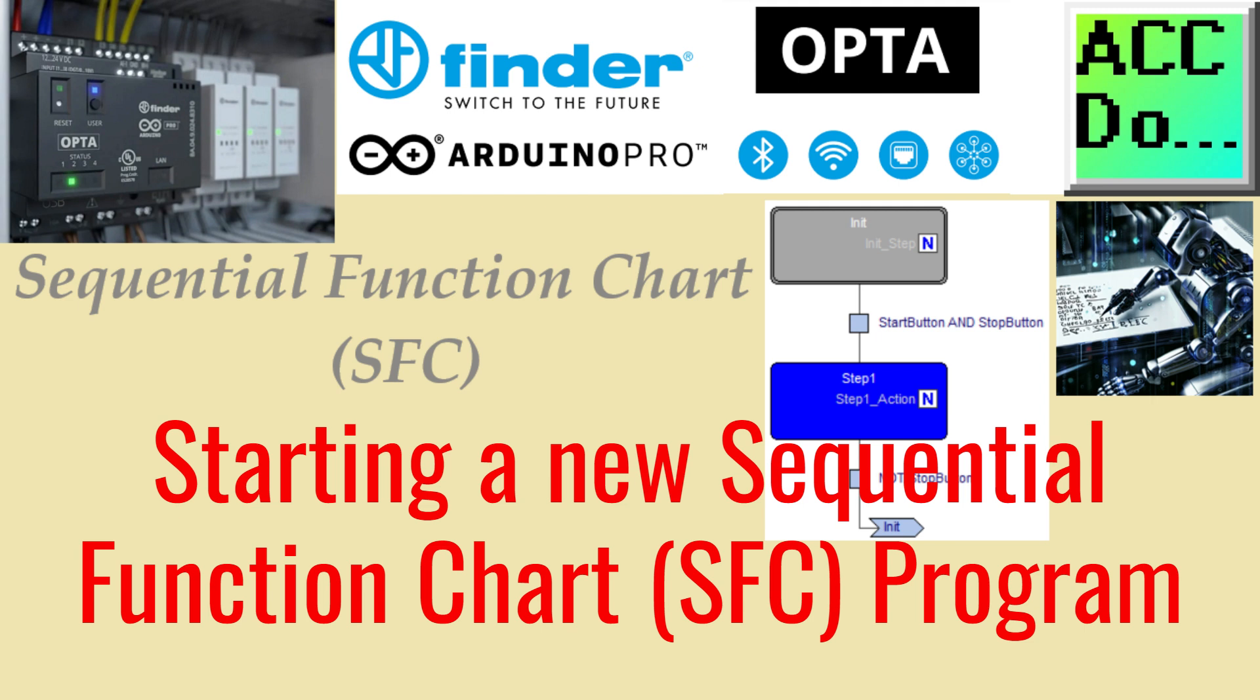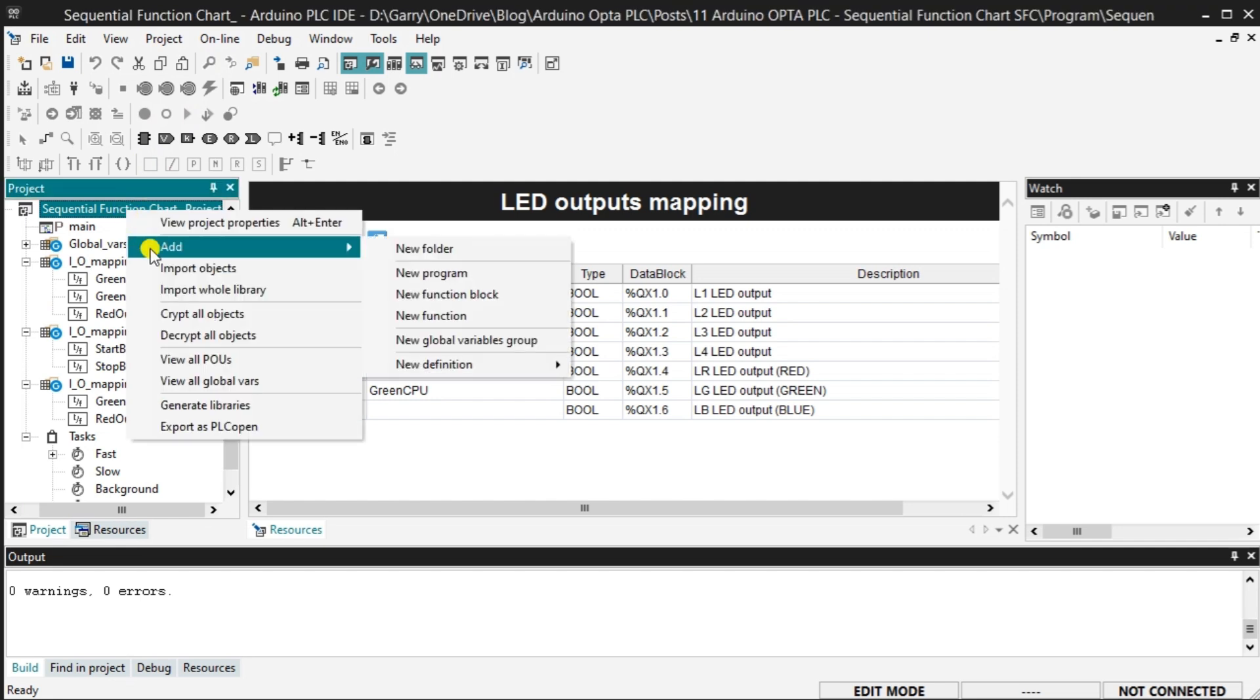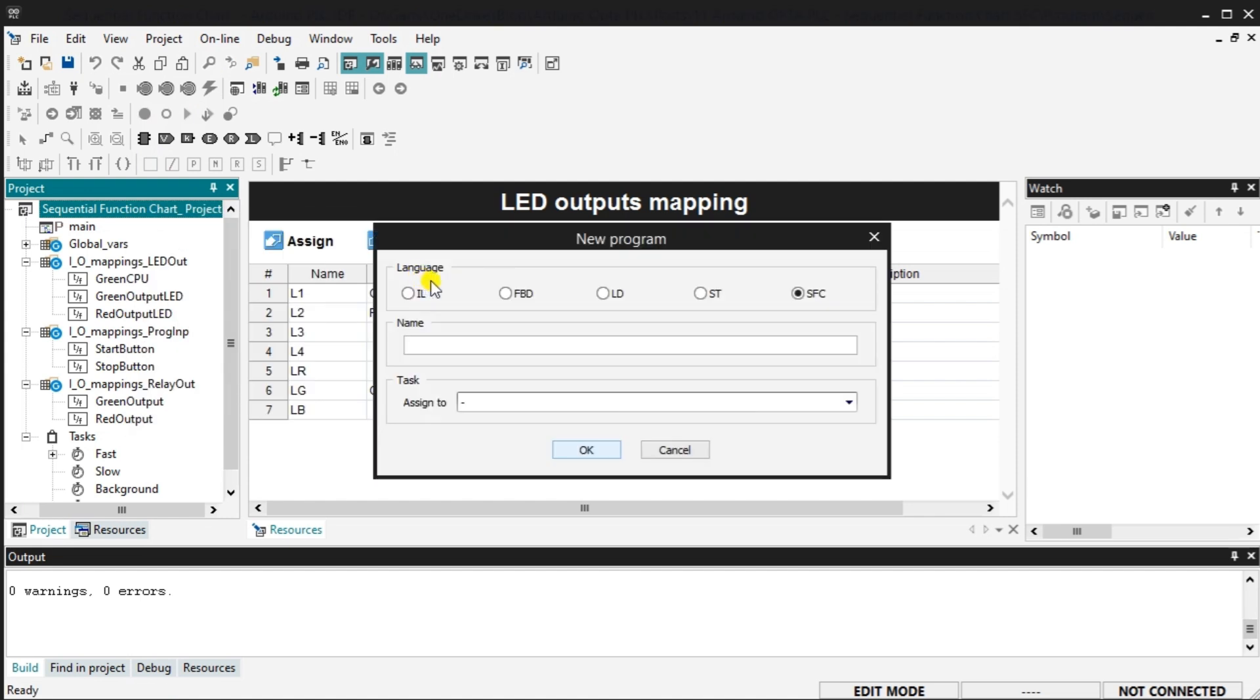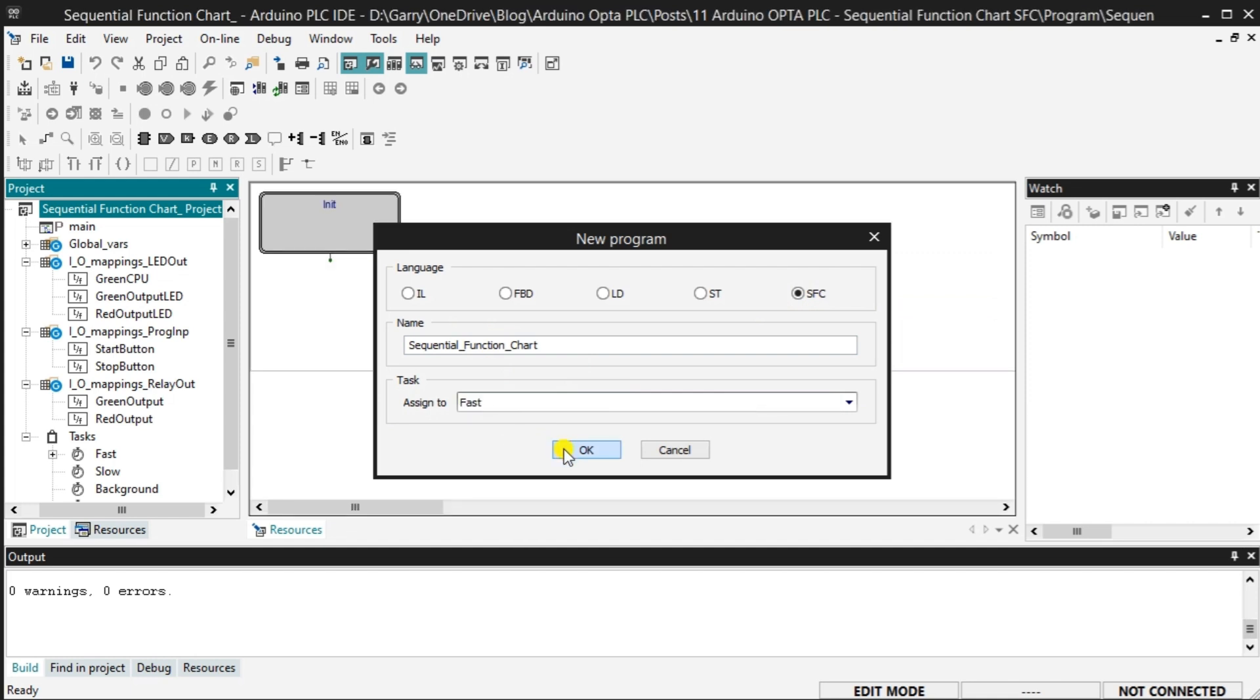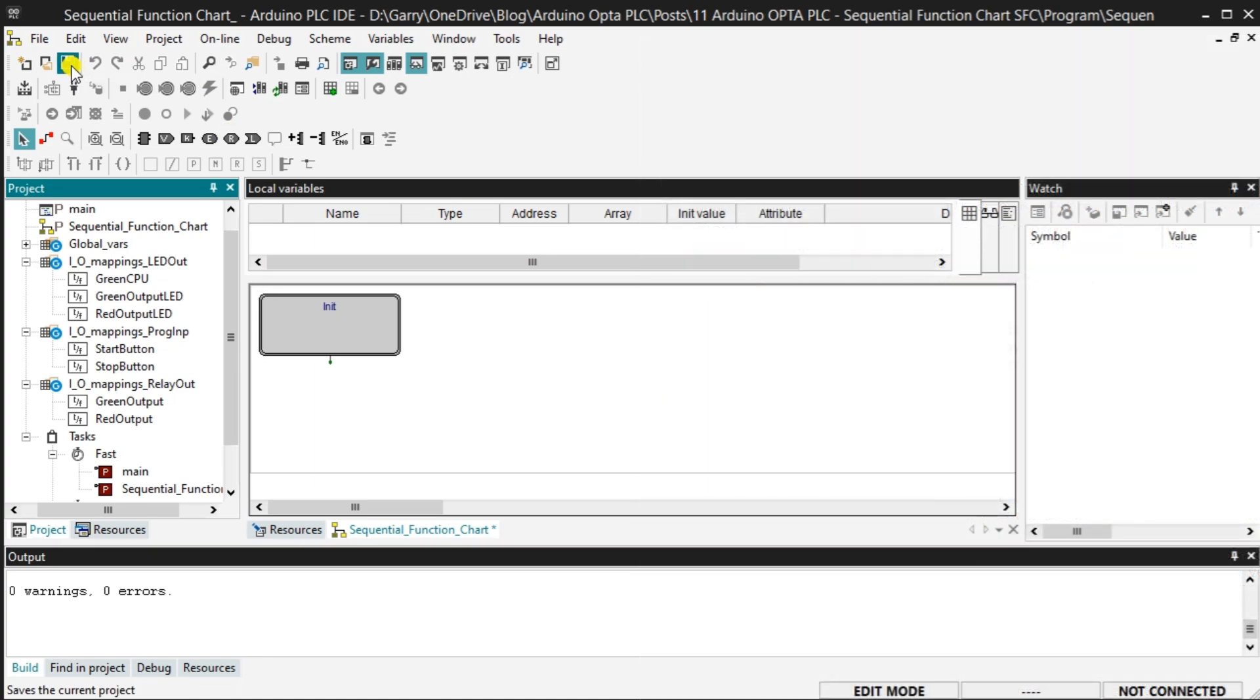Select Project New Object New Program from the main menu to start a new program. You can also do this by right-clicking on the project name and selecting the new program under the add heading. The new program window will be displayed. We will use a sequential function chart, SFC, in our example. Select SFC, name it, and assign the new sequential function chart program to the fast task folder. The program name cannot have spaces. Select OK. Our new SFC program will now be displayed in the work area. Save the Opta PLC program.